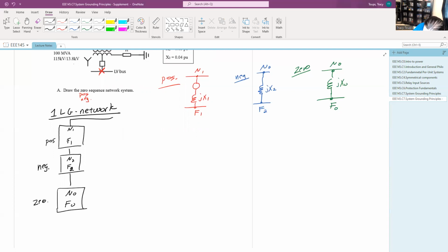And this is all in series, and we are adding a resistor in the network for the single line to ground fault. So we're going to have to put a resistor here as well. But the rule here is all impedances we put in, through either a tree branch impedance or a resistor we add on purpose, we have to multiply by 3 to add it into the network.